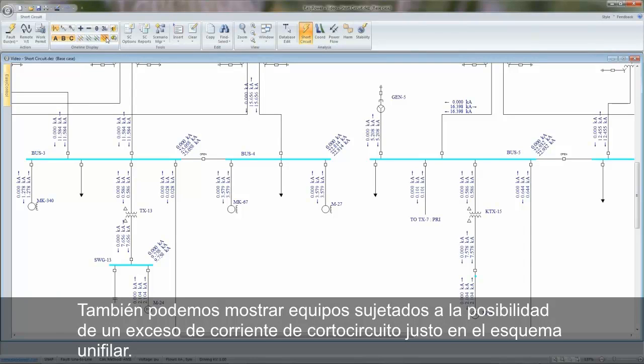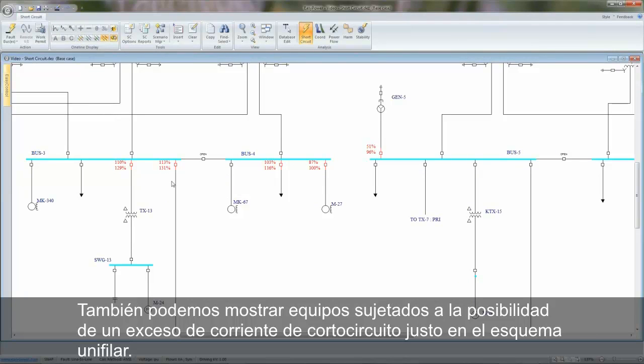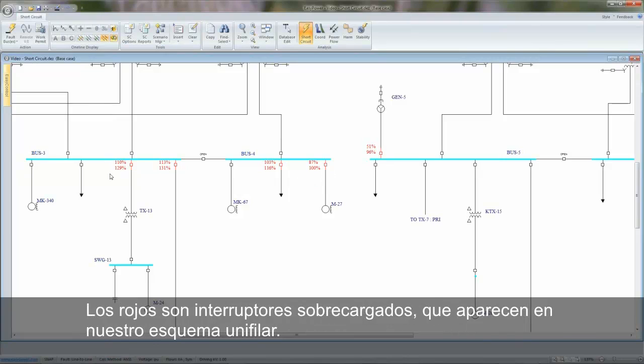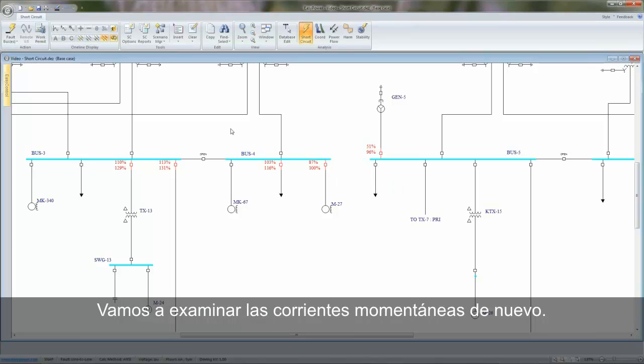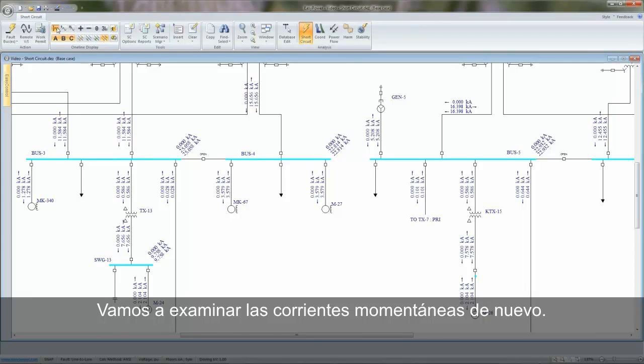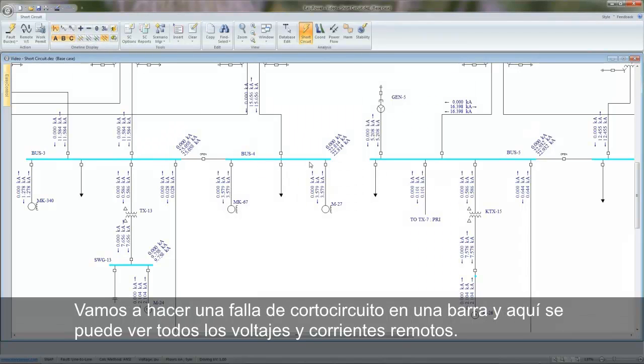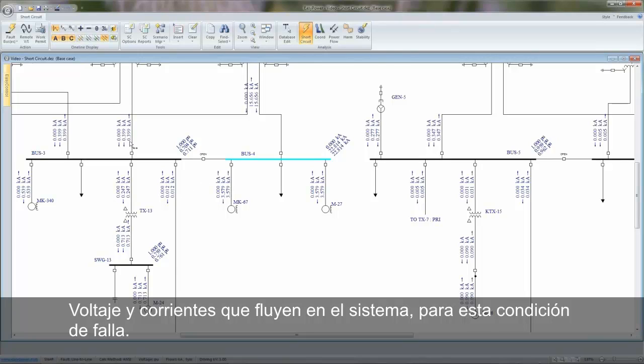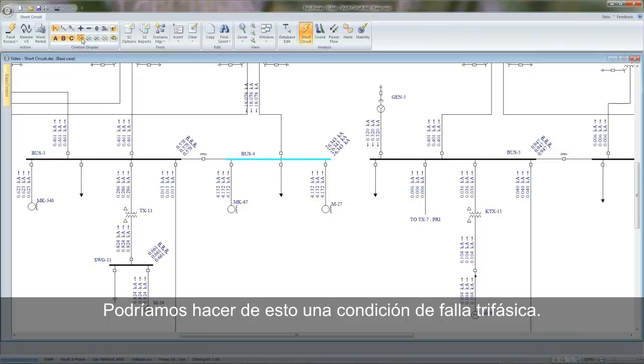We can also show over-dutied equipment right on the one-line diagram. The red ones are over-dutied breakers appearing right on our one-line diagram. Let's look at the momentary currents again. Let's fault a single bus, and here you can see all of the remote voltages and currents that are flowing on the system for this fault condition. We could make this a three-phase fault condition.